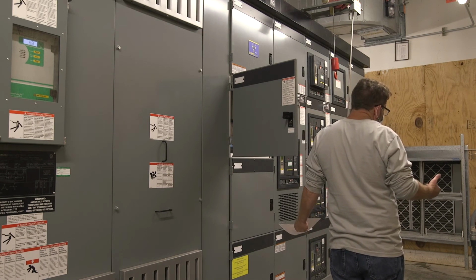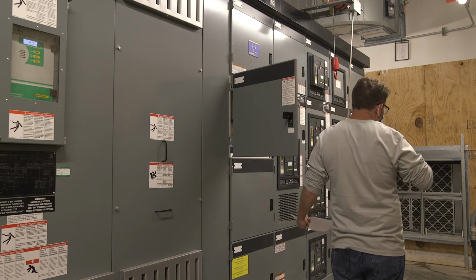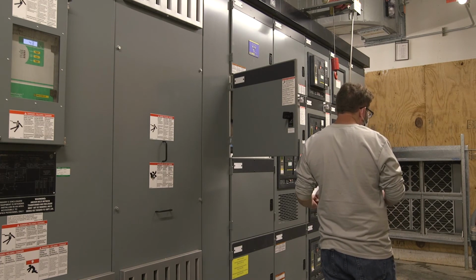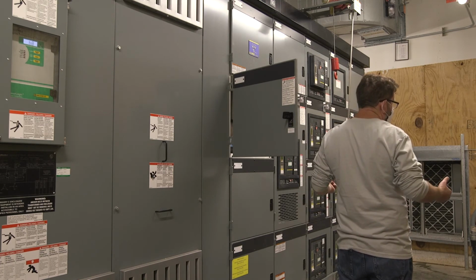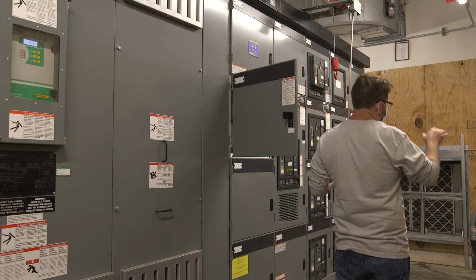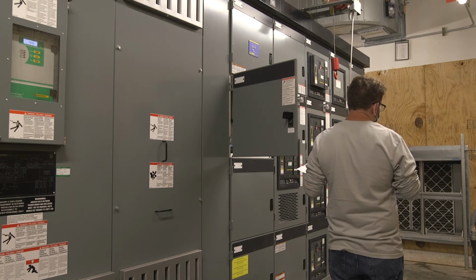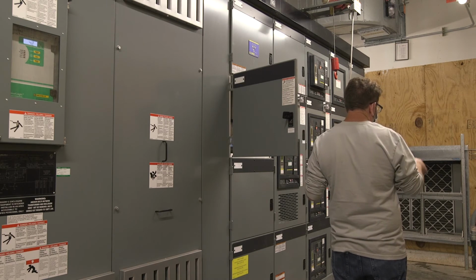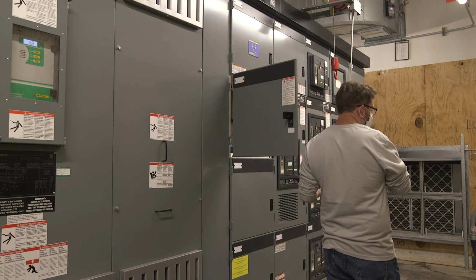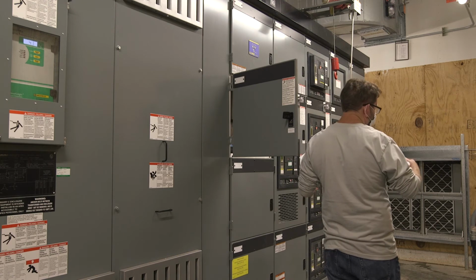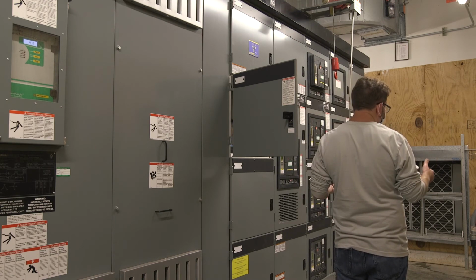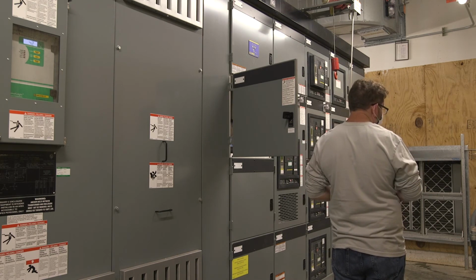They will go bad. They have a long life, but the more surges you have, the more of that life is used up. When you have a surge, the surge arrestor will shunt some of that voltage off to ground. So how much of that life you've used up depends on how big of a surge you have and the duration of the surge.